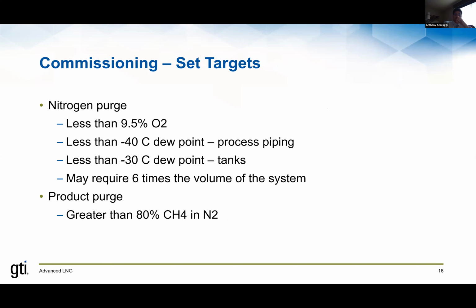You set commissioning targets, critical. Make sure that you've done your analysis, and you have your go points. We're going to purge the system, and these are examples here. This is not something that you take away and use as definitive points for your system. Through analysis, you determine what your targets should be. So, for example, in nitrogen purges, this is typical. Make sure you've reduced the oxygen content in the system to less than 9.5%. If you're drying out pipes with the nitrogen purge, you want your dew point to be less than minus 40 degrees Celsius. And when you're drying out your tanks, you want your tanks to be less than minus 30 degrees Celsius before you can feel comfortable introducing LNG into the tanks.